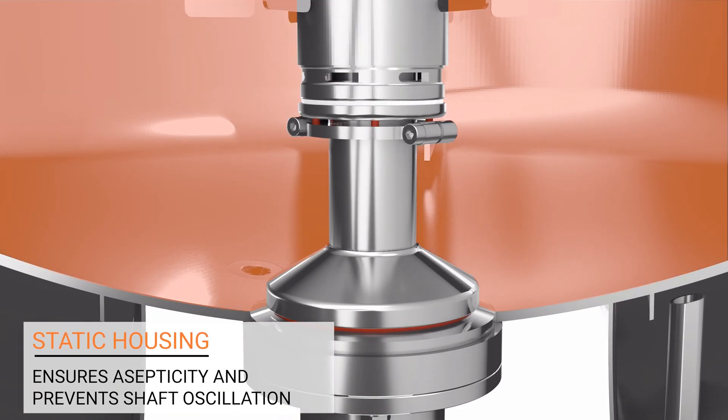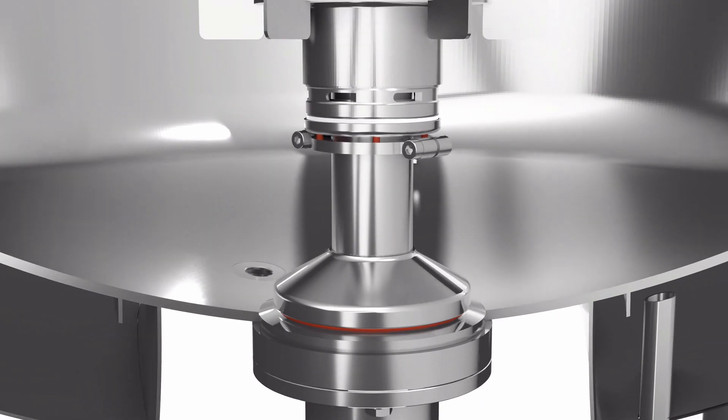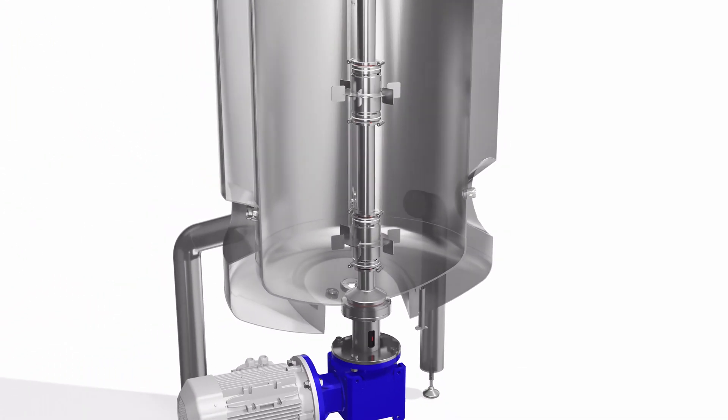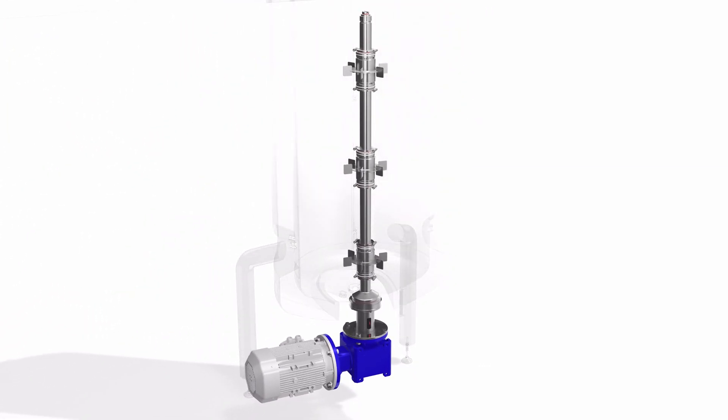Considering that the housing is static during agitation, the vessel remains hermetic at all times, even if a mixer failure takes place. Additionally, shaft oscillation is fully eliminated, which is a difficult task for most traditional drives.